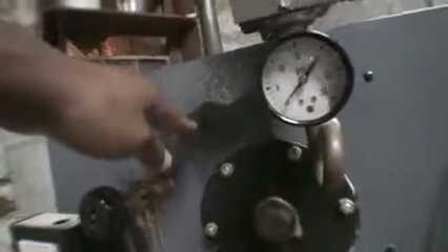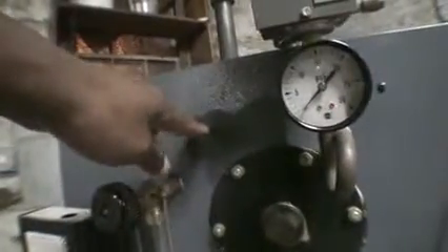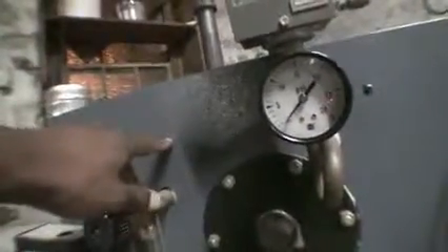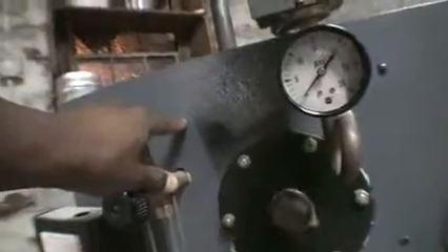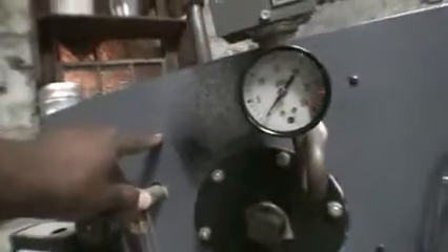So the only reason a hot water boiler is more efficient, or gets more BTUs into the water — remember, into the water — it's not more efficient in general, just more BTUs go into the water. That's because when you have steam, your water level cuts off here. You have gases or flame coming up from the bottom, and the most it can heat up is about halfway, with the rest just going up into the air and out through the exhaust pipe.